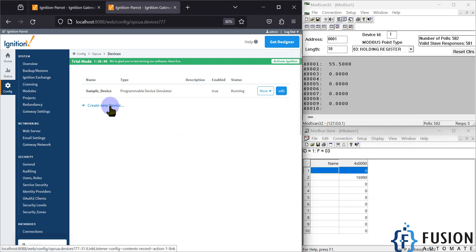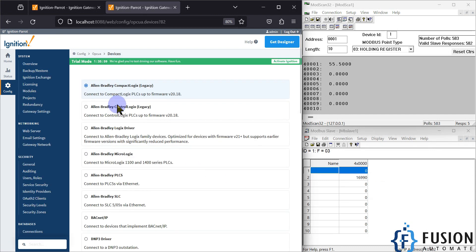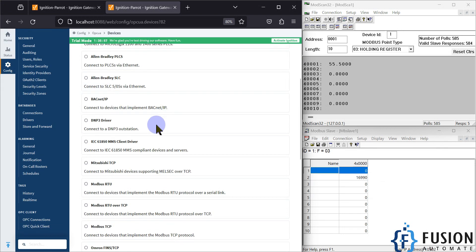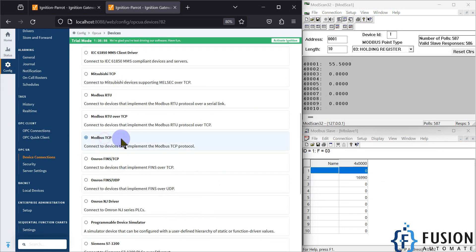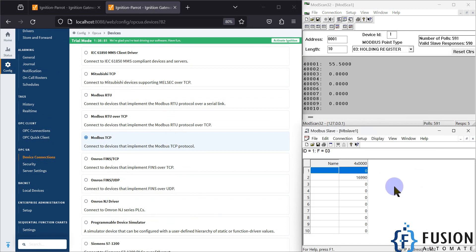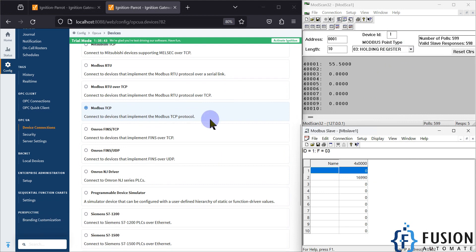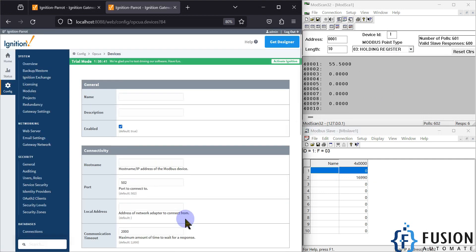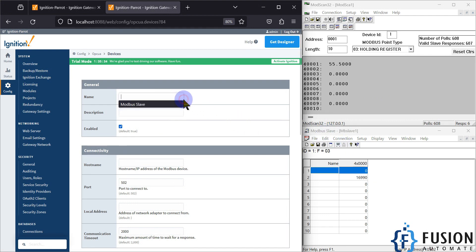What we want to exactly do is read and write floating point values from our Ignition SCADA to our Modbus TCP device. First of all we have to create a new device. We are going to create a new device and our device type will be Modbus TCP, because it's our Modbus TCP server and we are connected with our Modbus TCP server in Modscan using Modbus TCP IP communication. So we have to select Modbus TCP and press Next. Now, what will be the name of your Modbus TCP device? It will be Modbus Slave.